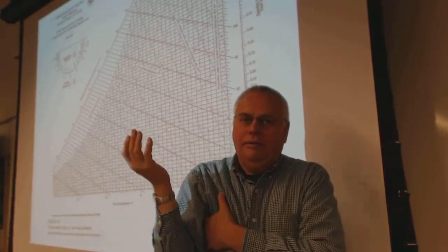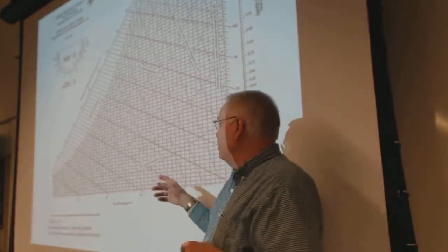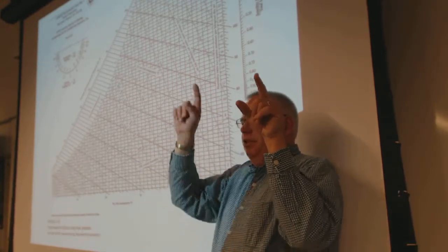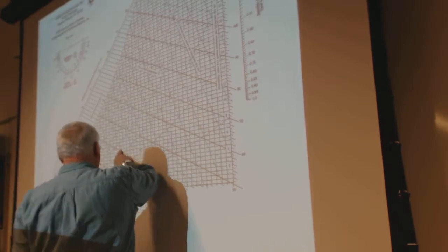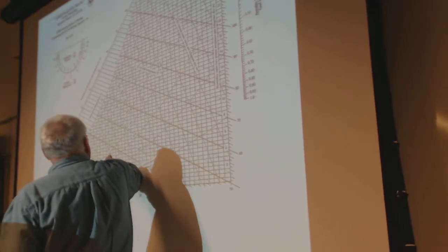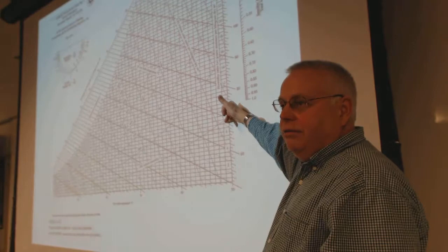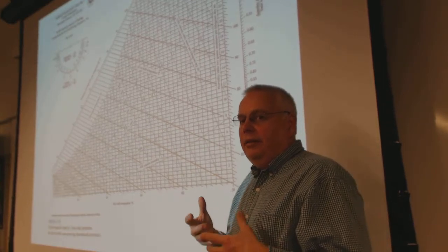And that's, this room is not humidified. If you look, there's a, above the microwave in the back of the room, if you look, there's a chart. It's another version of this chart from a different company. It's got color. It's pretty. But, it also tells what the temperature and relative humidity outside are, and what the temperature and relative humidity inside are. And, almost any day, if you look at that, if it says outside, it's 10 degrees and 80% relative humidity. And, if you heat it up, it'll say, indoor is, you know, like, maybe it says, 21 degrees. And, if it's in 10 and 80, it's going to say, like, 21 degrees and, 37% relative humidity. And, really, what's happening, that same moisture, they didn't add any moisture. It's the same value that you have, same amount of moisture. But, since you warmed it up, it's farther away from its saturation temperature. And, that makes it a lower relative humidity.